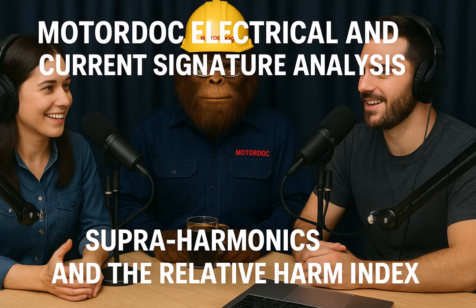Not just, is there a problem? Sure. But potentially, how significant is this problem? Are there general dB thresholds that signal, uh-oh? Yeah, there are rules of thumb. If a defect signature pops up more than, say, 5 dB above the usual noise floor, or if it's above about -70 dB, when the noise floor itself averages around -85 dB, specifically for things like stator slot signatures and winding stress, that's usually considered significant, worth looking into further.